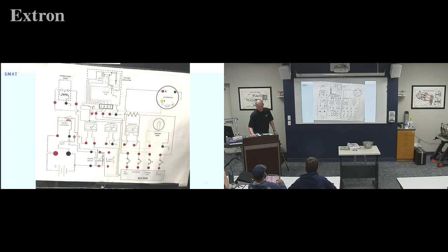Remember, these are vibrating contacts or vibrating points. We don't use these much anymore, so even with that logic, you might think we could update this with the vibrating contacts. We're looking at a couple different contacts. These are normally open, and they close when we say, hey, start making power. I use that phrasing to say S, if I supply power to S, I'm going to go through that little coil right there, and that's going to close this set of contacts, which is how that's supposed to be drawn, to say start making power. So if we supply power to that S terminal, we're telling the voltage regulator, start making power.